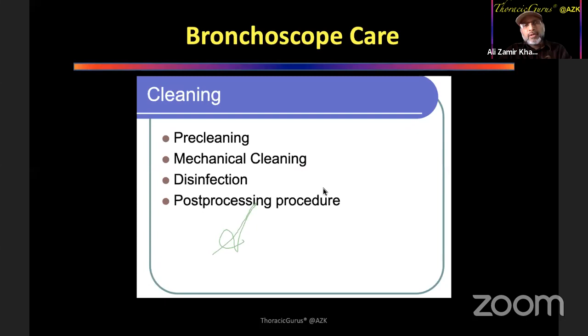So there are a lot of things that you need to do when you have to take care of the bronchoscope. And particularly when the bronchoscope comes in the hands of an inexperienced person, inadvertently, when they're manipulating the bronchoscope or when they're putting in probes or needles through the bronchoscope, they may actually damage the bronchoscope. And this is a classical example of damage in the sheath of the bronchoscope where there are bubbles coming out. This is called a bubble test that you do when you put the bronchoscope under water and you watch for air coming out from the side of the bronchoscope. If your channel is straight, the air should come out from the end of the bronchoscope. Anything coming out from the side suggests that there is damage to the covering sheath of the bronchoscope.